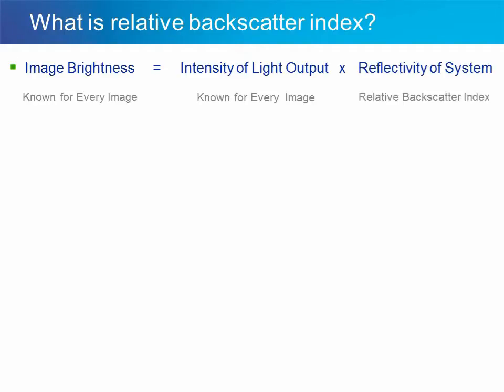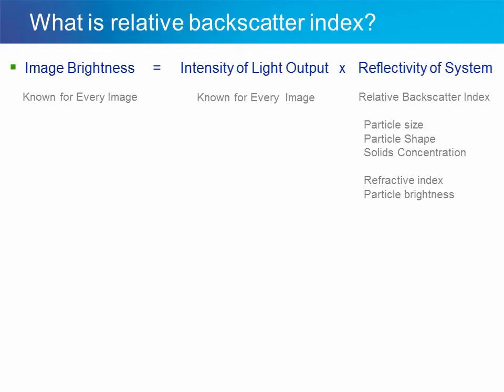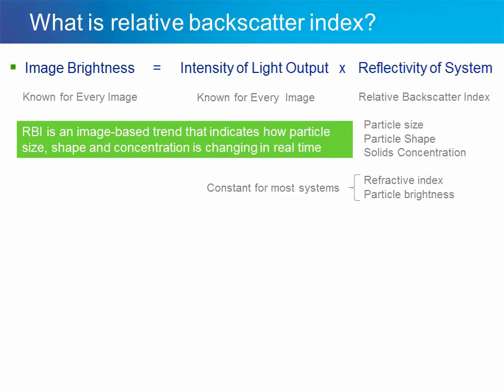The image brightness is known for every image, as is the intensity of the light output. The reflectivity of the system we call relative backscatter index. RBI is a function of particle size, particle shape, solids concentration, and the refractive index of the system as well as particle brightness. For most particle systems, refractive index and particle brightness remain constant, meaning RBI is an image-based trend that indicates how particle size, shape, and concentration is changing in real time.